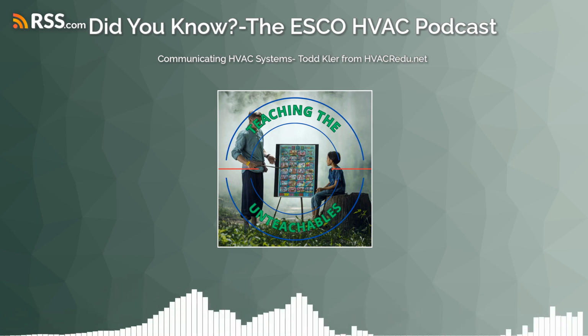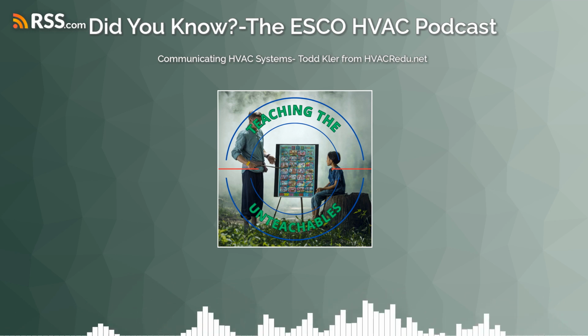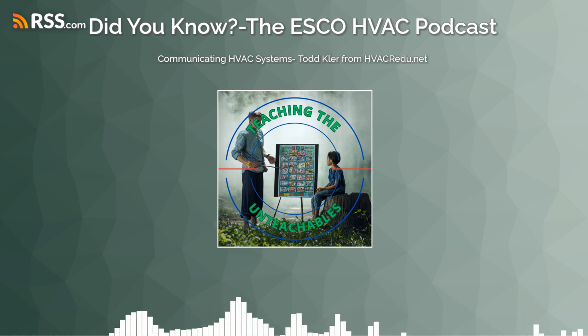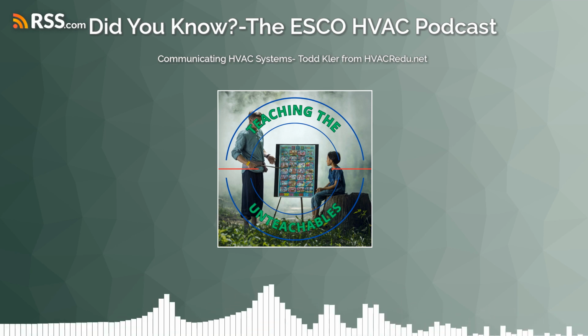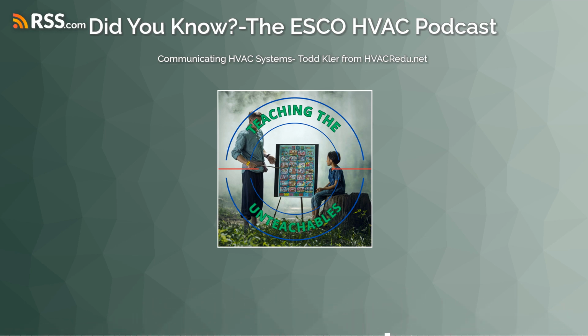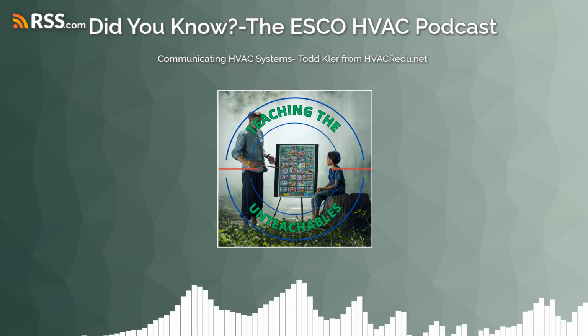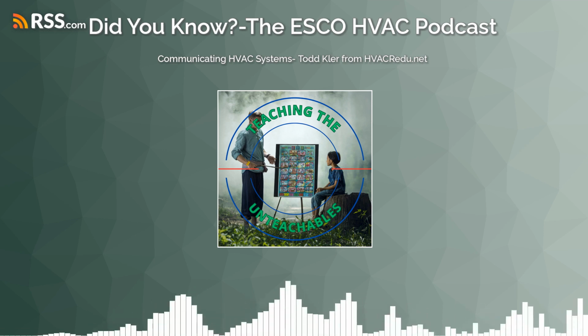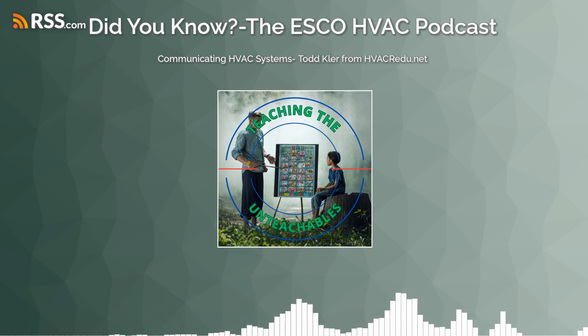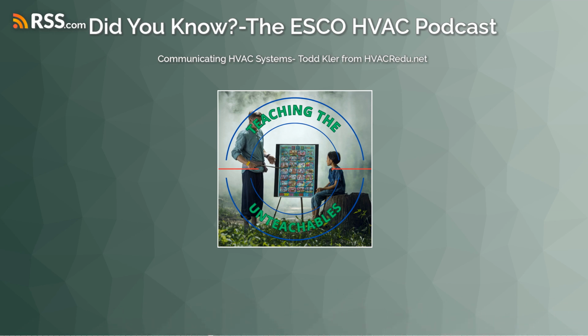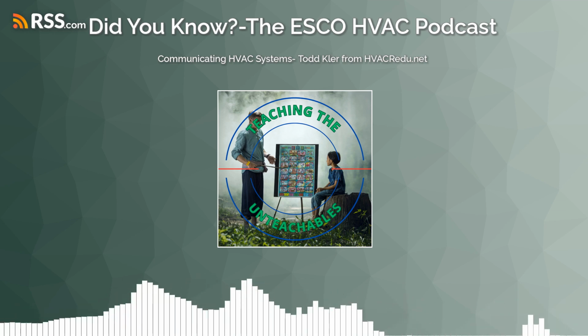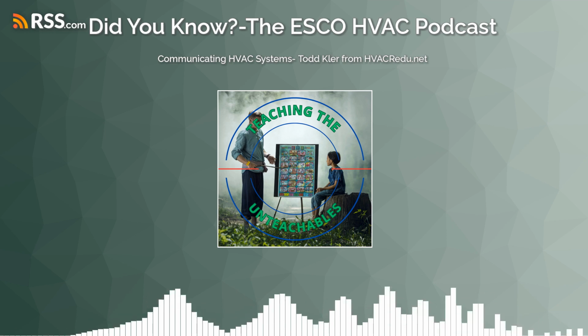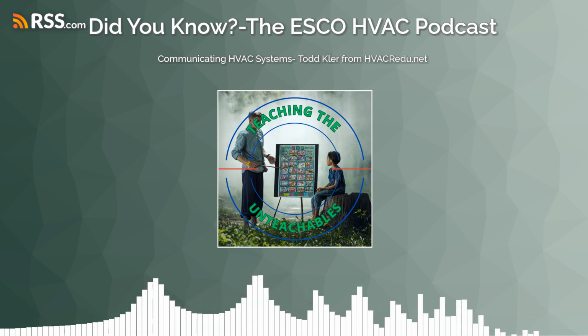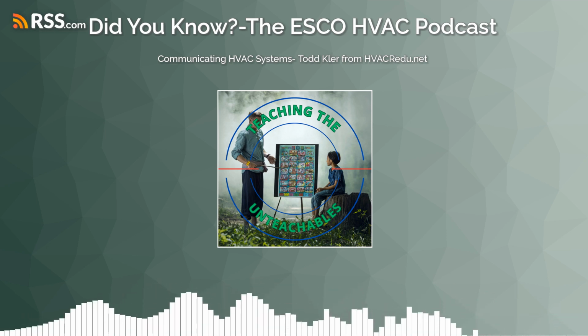Yeah, you made mention that we get that transformer of 24 volts from our indoor unit. Do keep in mind this is unitary, usually a split system. Now, when we do talk about ductless split systems, then it's coming from the outdoor unit. So just keep that in mind. Everyone's going, hey, time out, that comes from the outdoor unit. Yeah, in a ductless system. Exactly. And our inverters that have a power supply at the outdoor unit will typically have their own as well. And we'll show you a little bit on that, what that one is.